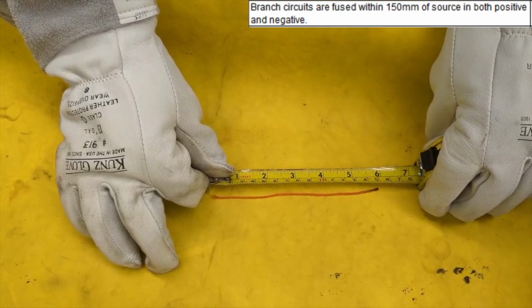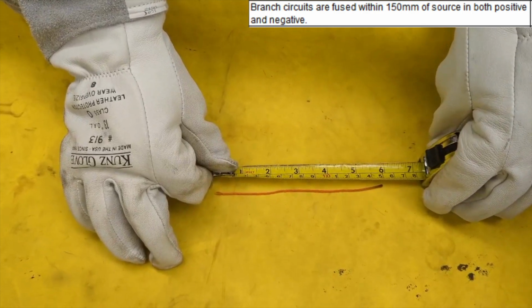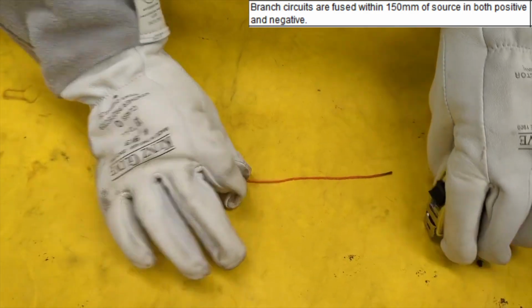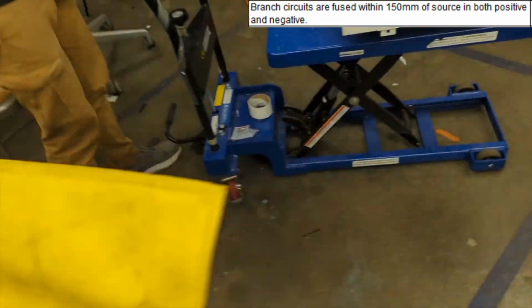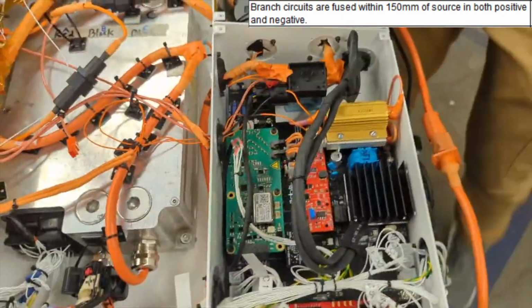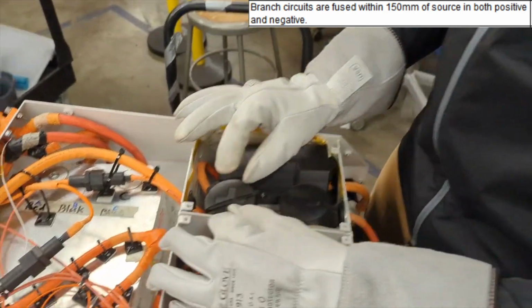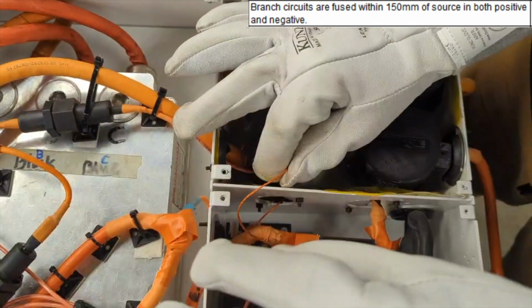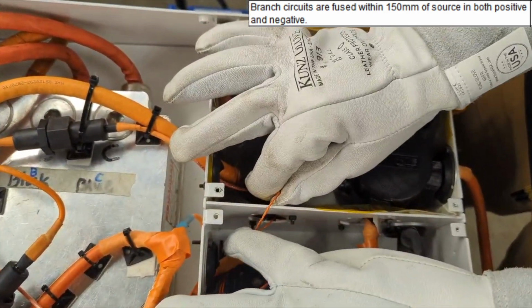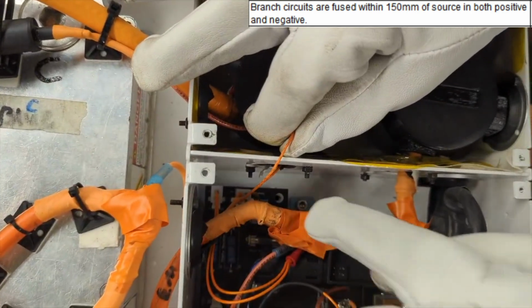Now I will demonstrate that all of our branch circuits are under 150 millimeters using this string. Coming into this section, our battery plus branch circuit for the pre-charge goes from the AIRs cover into the AIRs terminal to the base PCB, and as you can see, the string is much longer than the wire attached.